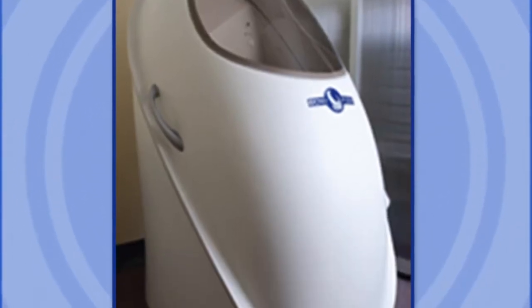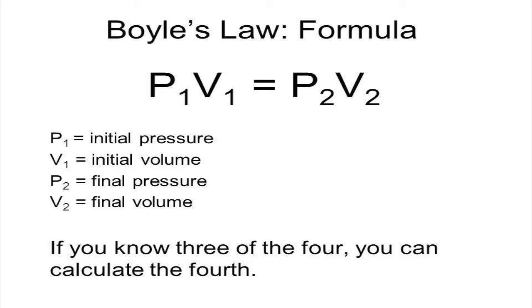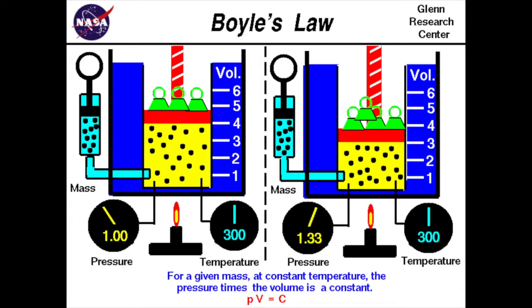So how does a device like the Bod Pod actually work? ADP uses the relationship between pressure and volume, also known as Boyle's Law, to measure the volume of a person's body when they're inside an enclosed space. Boyle's Law states that volume and pressure vary inversely with each other through the equation P1V1 equals P2V2. Using this equation, the Bod Pod is able to determine a person's body volume by measuring pressure responses to small volume changes in an enclosed chamber.